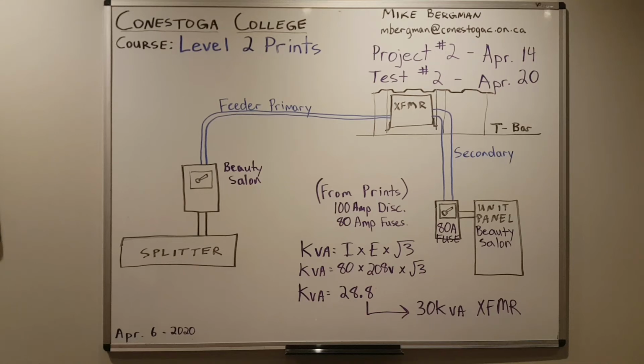So to calculate the transformer for each unit, I want you to look at the size of the disconnect. So for the beauty salon, it was a 100 amp disconnect. What can I load that disconnect up to? I can load it up to a maximum of 80% of 100. So I can put 80 amps on that disconnect 100% of the time. Now, I know the beauty salon has 80 amp fuses, so we'd be 80% of 80 amp fuses, but we could increase capacity with the beauty salon.